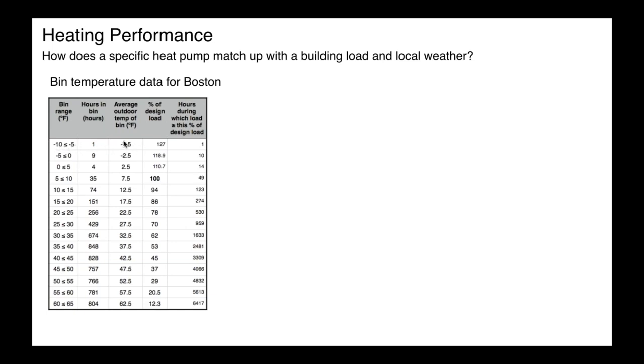So we're going to use that as our air temperature that the heat pump is operating at. And this represents percent of design load corresponding to that outdoor temperature. So our outdoor temperature was 9 degrees at design. That represents approximately 100%. Now, the narrower you can make these bins, the more accurate the calculation. I believe the ASHRAE data actually takes it right down to bins that are 1 degree Fahrenheit wide. It just means we have more calculations, but spreadsheets can handle that, no problem.